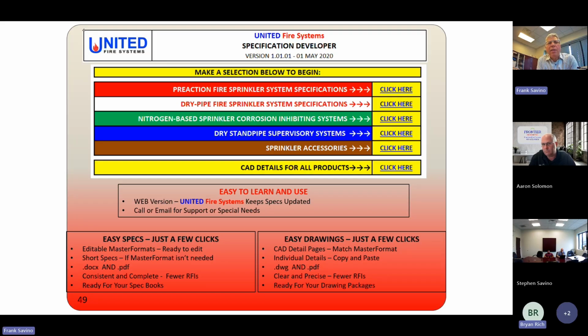The way I look at fire protection and suppression agents is that you have to have your bag of tools. You've got clean agents, you got dry chemical, you have fixed aerosol, you have CO2. You have sprinklers, deluge, water mist. They all have their strengths and weaknesses. And the story I gave you about the medical facility, if I didn't know about water mist, I could not have solved that problem for that medical facility. We would have been digging up the highway. So sometimes sprinklers are better for whatever reason. There may be a cost issue, or in the case of, say, central storage batteries, that's your solution. So I'm not really a big promoter that, hey, it's got to be water mist or anything. It's just one of the things in our bag of tricks that we have at our disposal.